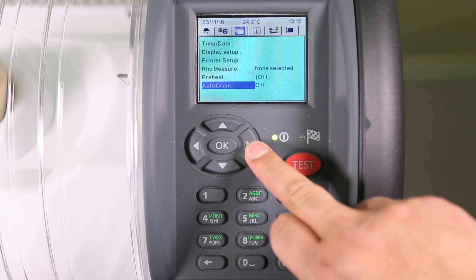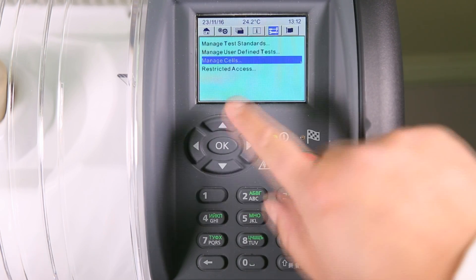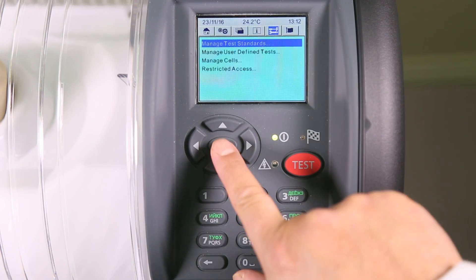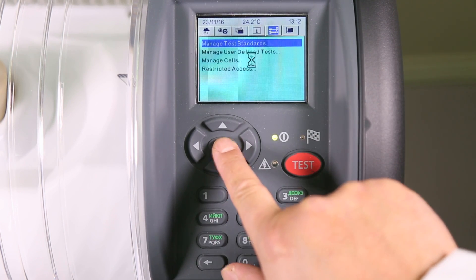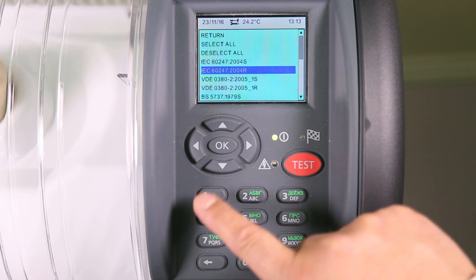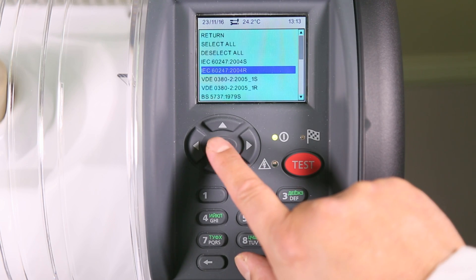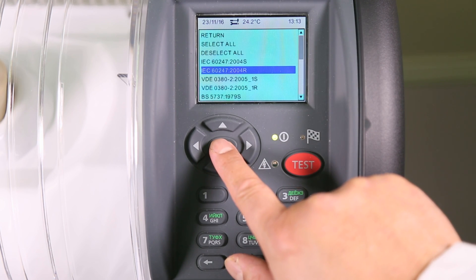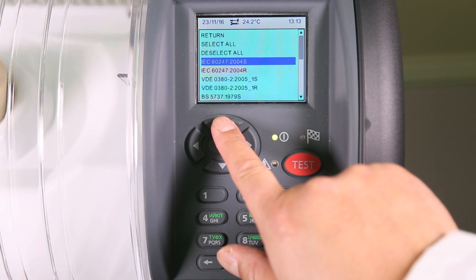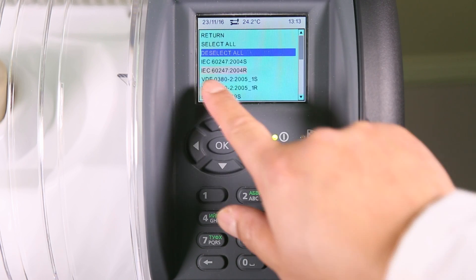First, select a test. To do this, go to manage test standards and press OK. You will then see a list of all the standards available for this instrument. Select the standard you require — you'll see this highlighted — then return.